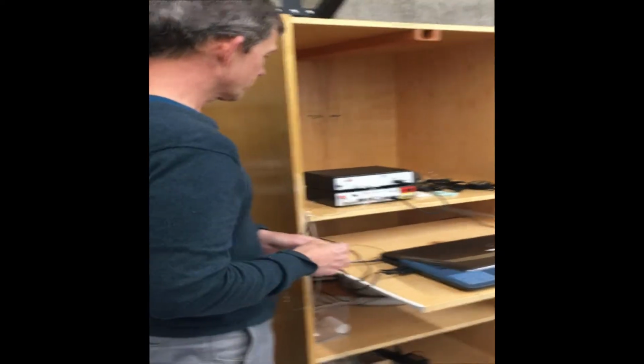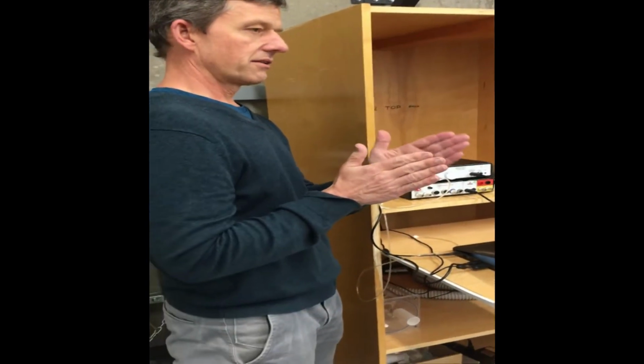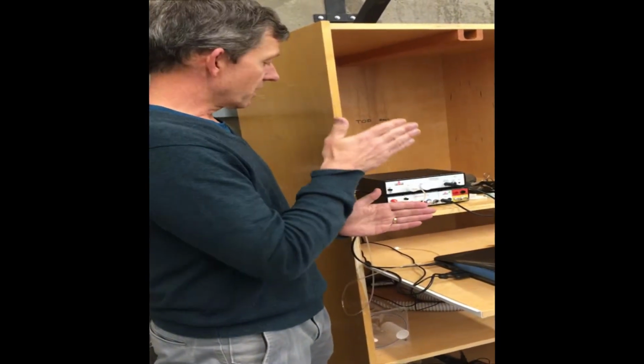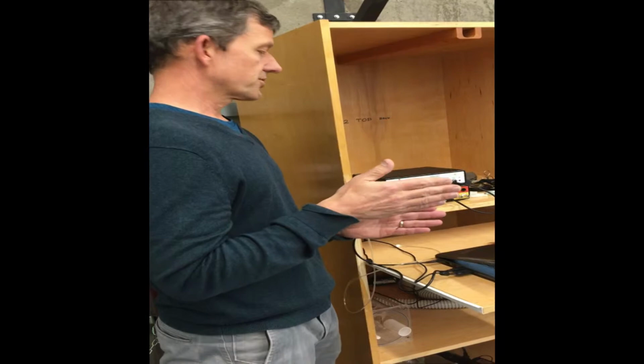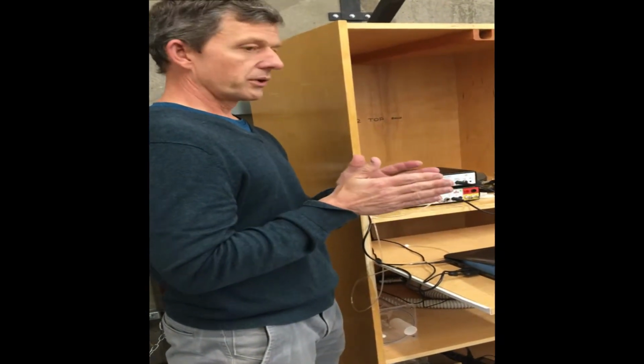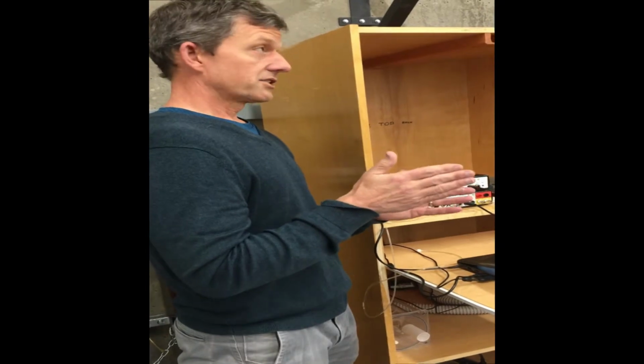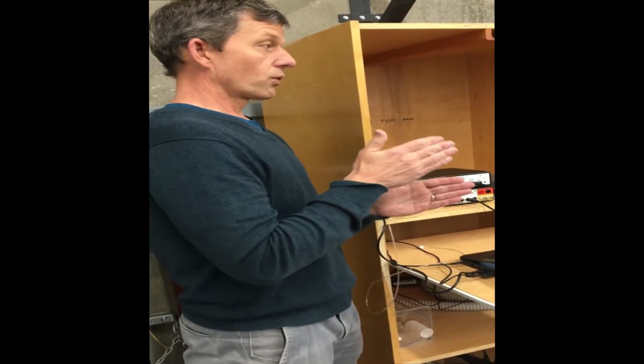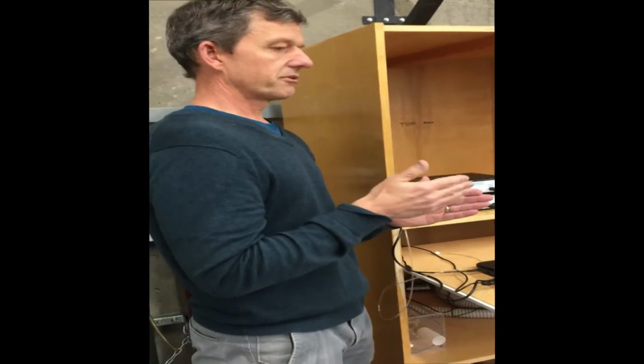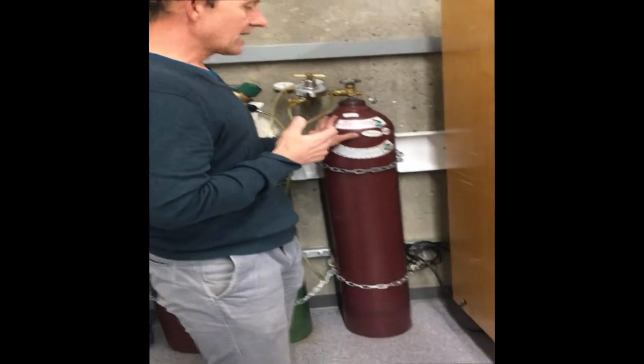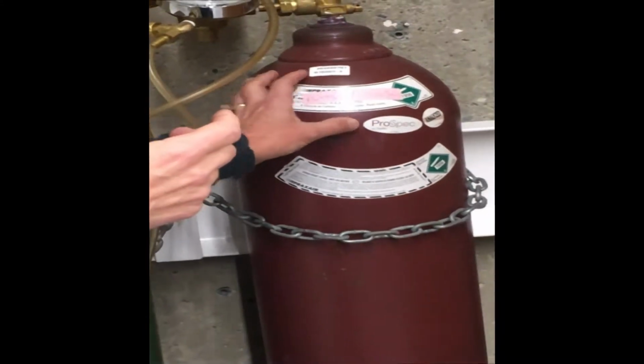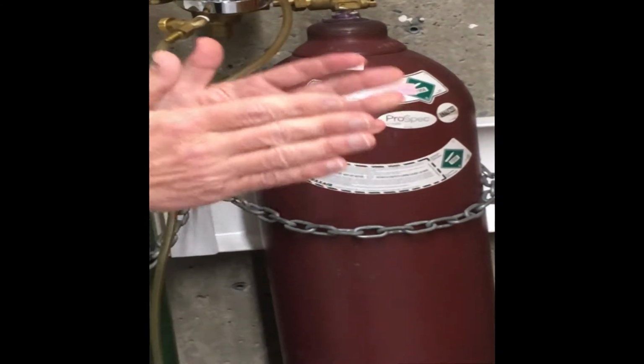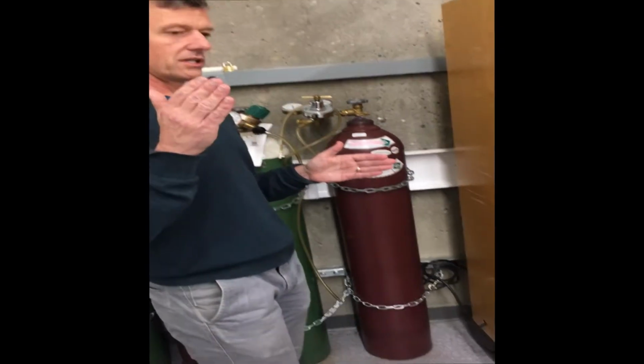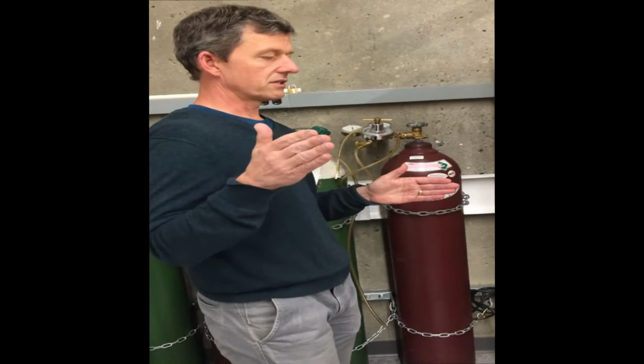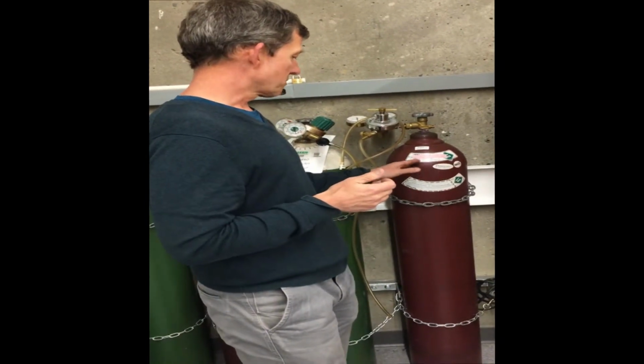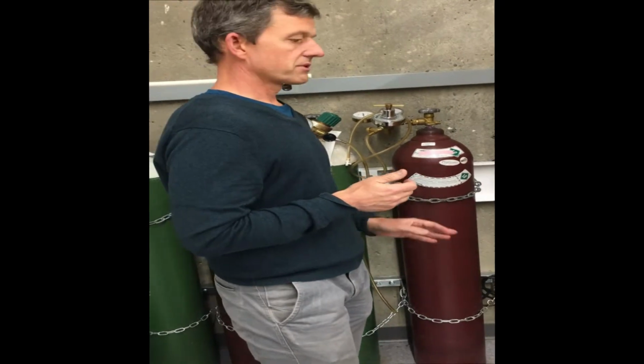When we calibrate, we actually use a calibration gas that's on the other end of the physiological spectrum. We know that room air is 20.93% oxygen and 0.03% carbon dioxide. We know that when we're doing our VO2 max testing and our breath hold, CO2 won't go above 5%, and oxygen shouldn't drop below 15%. So we have a calibration gas that has 15% oxygen and 5% CO2. That gives us our physiological range. The maximum is going to be 20.93% oxygen and 0.03% carbon dioxide, and on the other end of the spectrum, we're going to have 15% oxygen and 5% CO2.